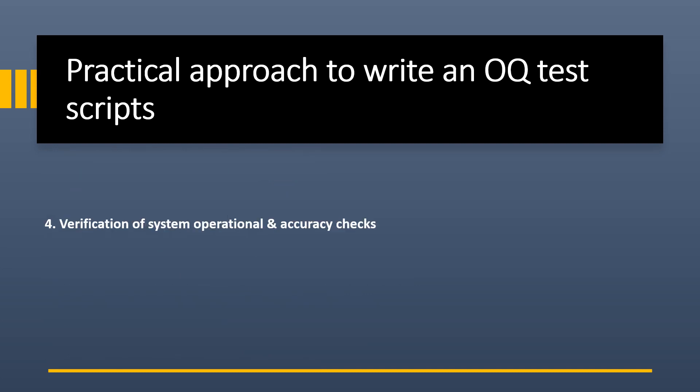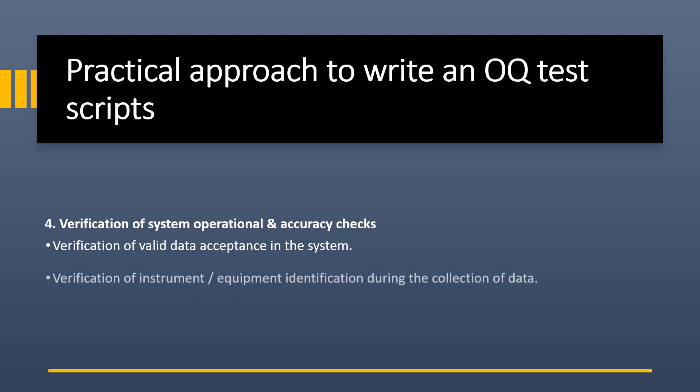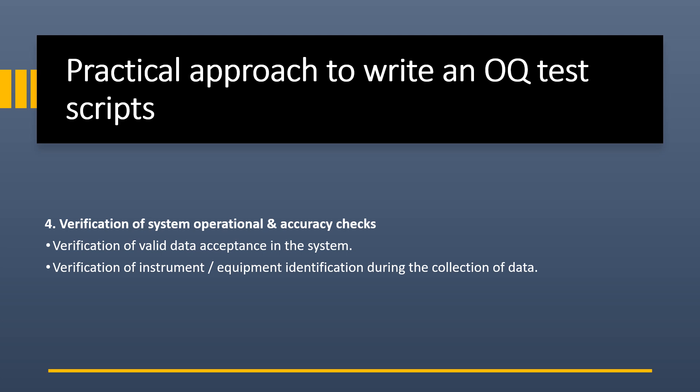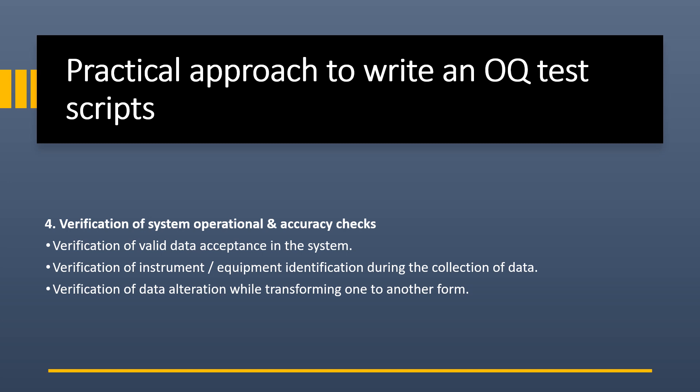Fourth is verification of system operational and accuracy check. This includes verification of valid data acceptance — the system must accept only valid data within acceptance limits. Next is verification of instrument or equipment identification during data collection — the system must capture instrument ID details in raw data and reflect them in the electronic report. Next is verification of data alteration during transfer — data transferred from raw format to report format must remain unchanged.